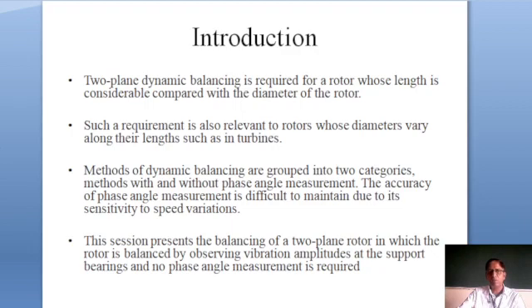In most cases the speed of the component or motor is not constant. Why? Because the electrical supply is not constant — there are fluctuations in voltage, and because of those voltage fluctuations the speed of the motor is also fluctuating. That is why correct phase angle measurement is very very difficult under these circumstances, and too much reliance on phase angle measurement is sometimes not recommended.